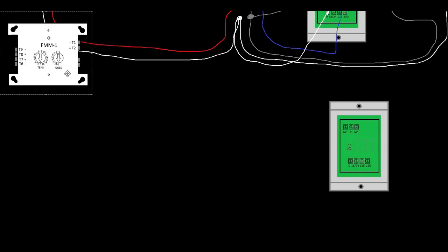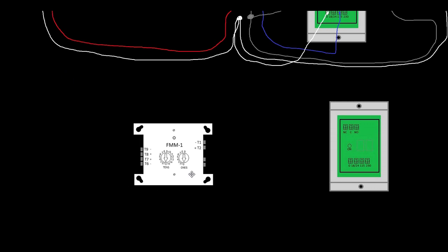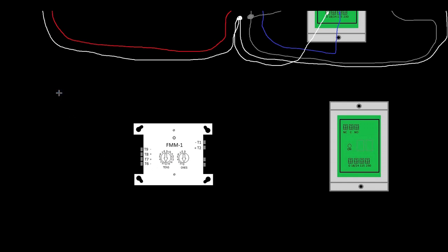Monitor module, obviously we've looked at in other videos, it gets SLC and then on terminals T6 and T7 it's just looking for a short and open or a resistor, that's how it supervises.